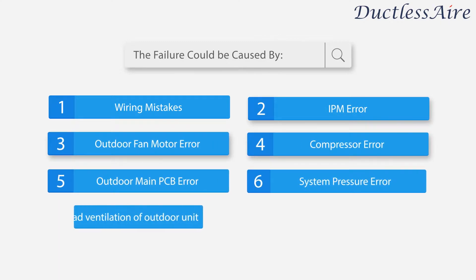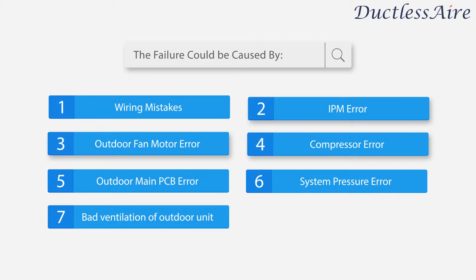The failure could be caused by: 1. Wiring mistakes; 2. IPM error; 3. Outdoor fan motor error; 4. Compressor error; 5. Outdoor main PCB error; 6. System pressure error; 7. Bad ventilation of outdoor units.